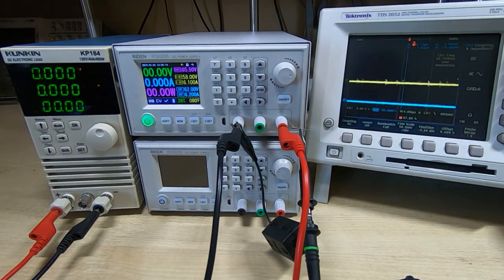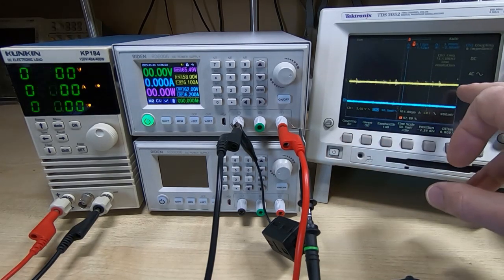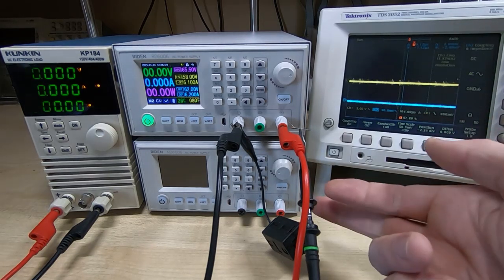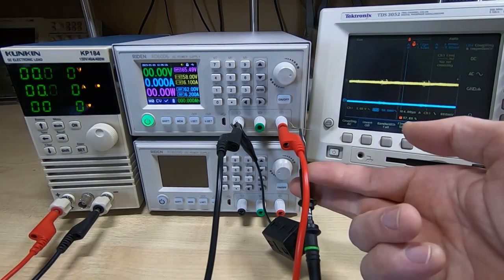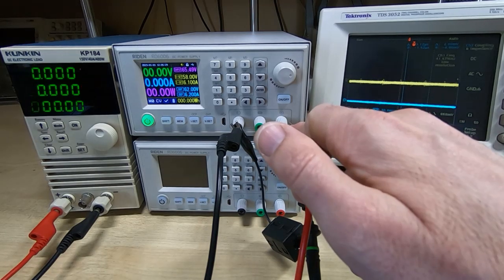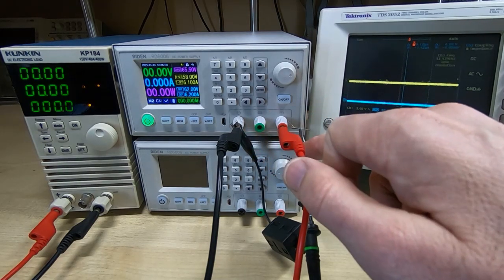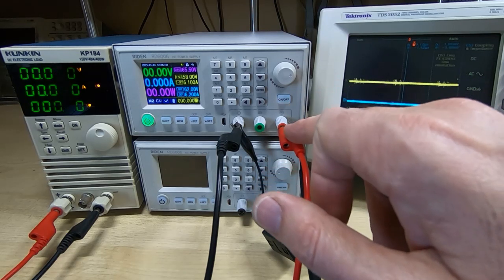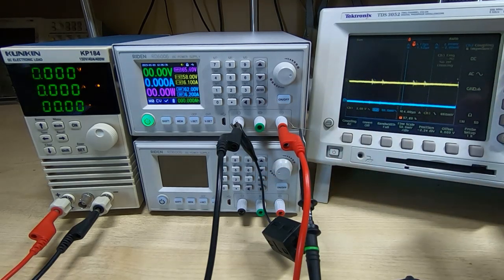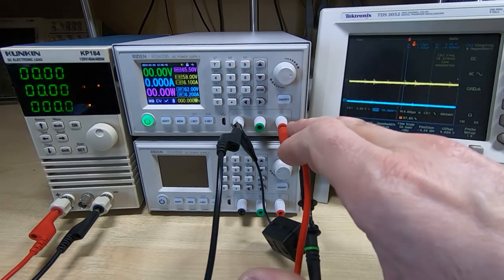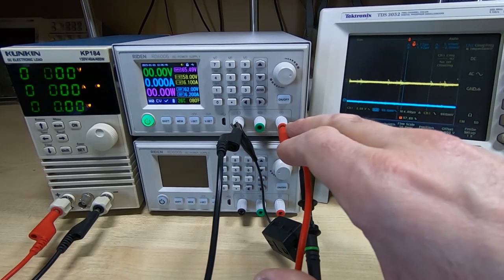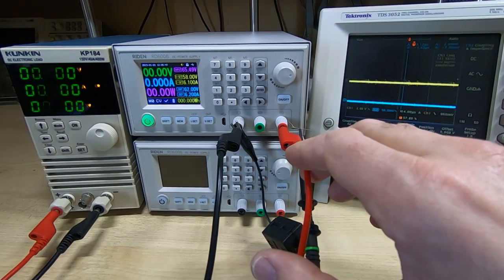So channel 2 is effectively the current we're seeing coming down the cable in isolation from the EM voltage emissions, if you like, that may be interfering or causing noise within the cabling going to the scope. Channel 1 on the scope, which is the yellow trace, is the actual AC voltage coming out of the supply. So I've got a small capacitor here, isolating the DC content from the supply because I'm not interested in that. I've got the scope set to AC for both channels, so what we're looking at is just the AC content of whatever's coming out of the supply, with the DC removed.